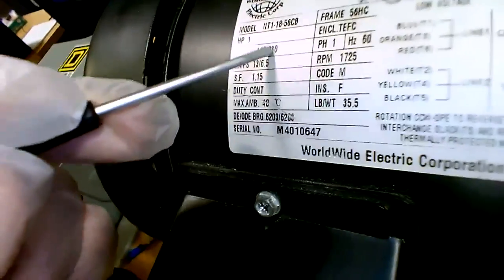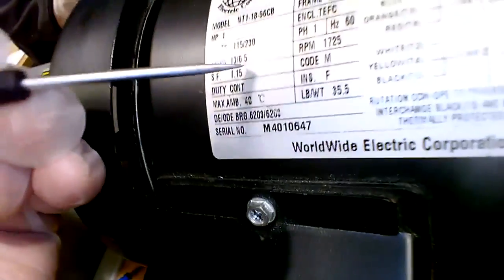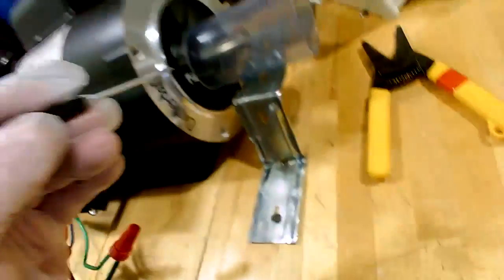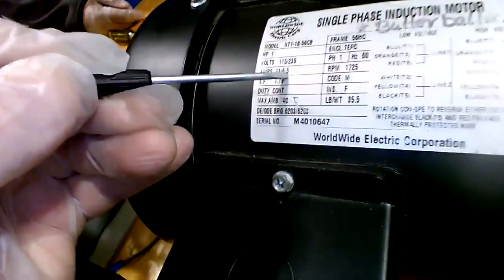We're running at 208, not 230, and we don't have any mechanical load that we're driving. If you have this hooked up to a pump or to a fan and you're driving a mechanical load, you're going to get somewhere in the range of 6.5 amps of draw when this is actually pushing something. If it's freewheeling, the amp draw is going to be less, but my point is, when you check the amps that way, make sure that it does not exceed what the nameplate says. If it does, there's something wrong.